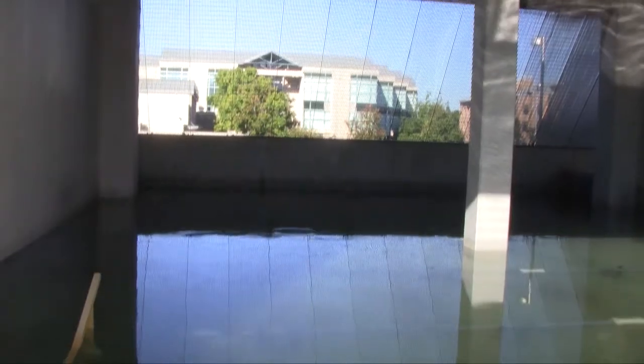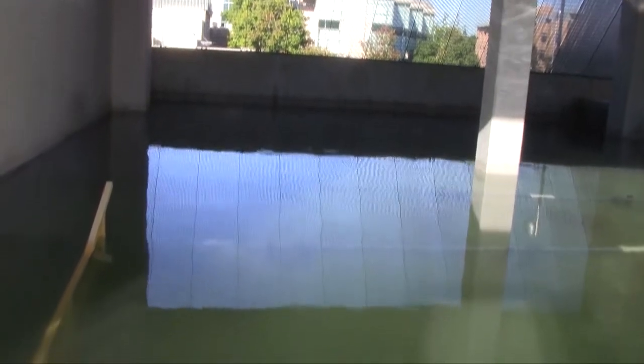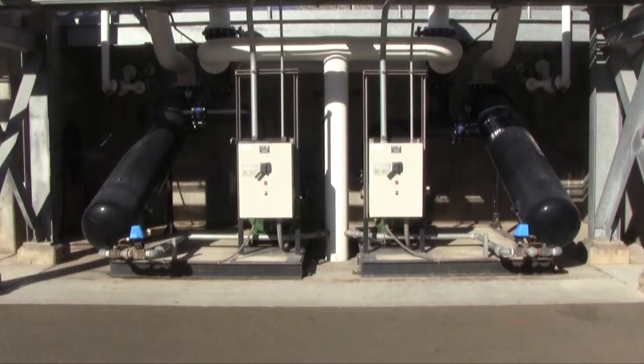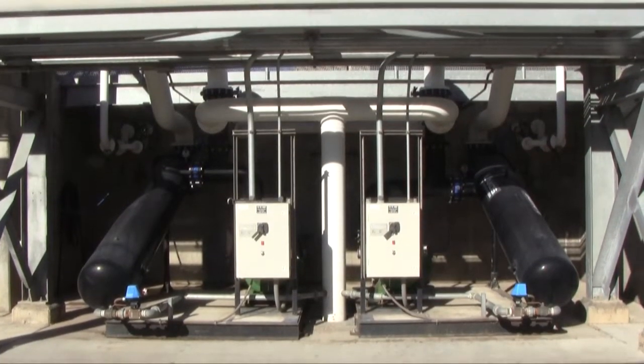We've got a chemical treatment program with oxidizing and non-oxidizing biocides. We've got corrosion inhibitors. Besides that, we'll install inlet screens for the circulation pumps. But basically, the Lakos system is primarily what keeps the towers clean of any particulate matter.